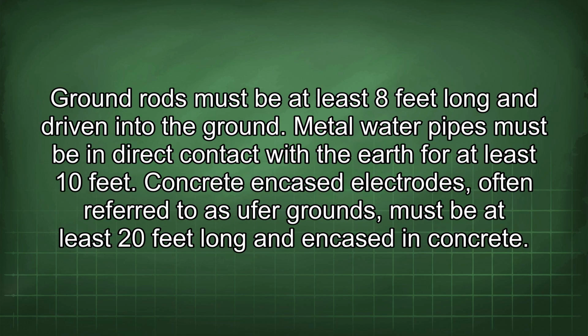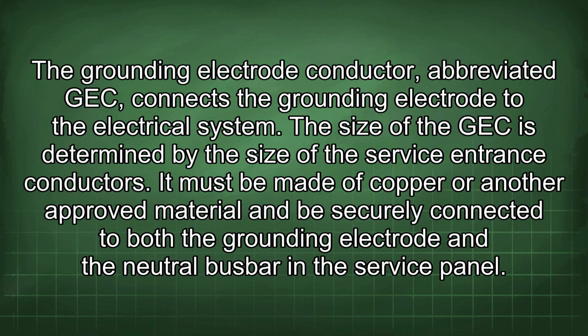Ground rods must be at least 8 feet long and driven into the ground. Metal water pipes must be in direct contact with the earth for at least 10 feet. Concrete encased electrodes, often referred to as Ufer grounds, must be at least 20 feet long and encased in concrete. The grounding electrode conductor, abbreviated GEC, connects the grounding electrode to the electrical system. The size of the GEC is determined by the size of the service entrance conductors.